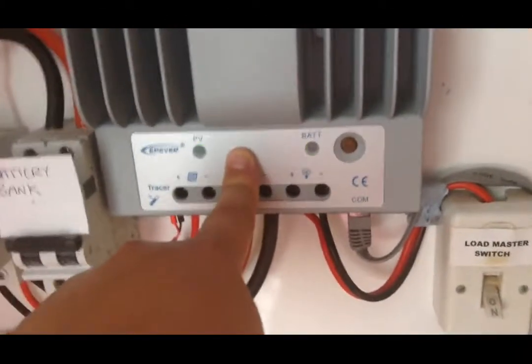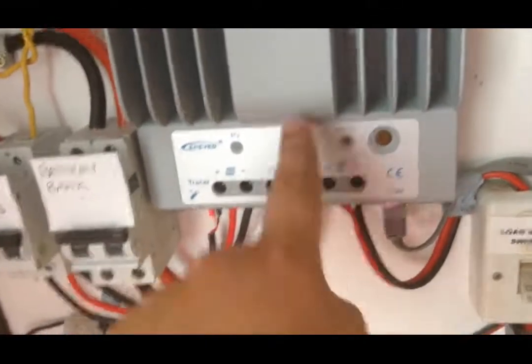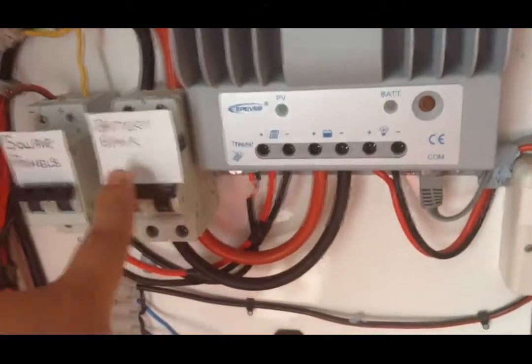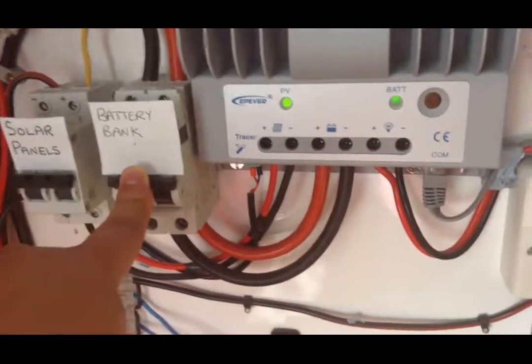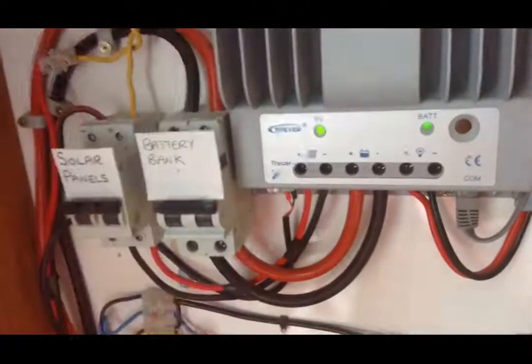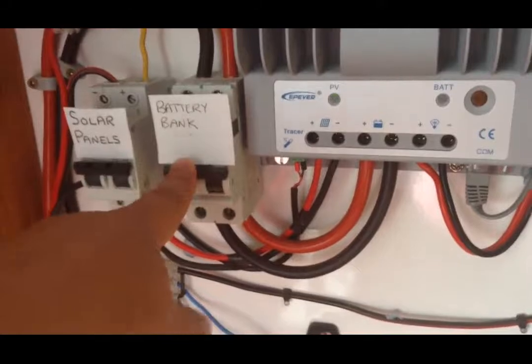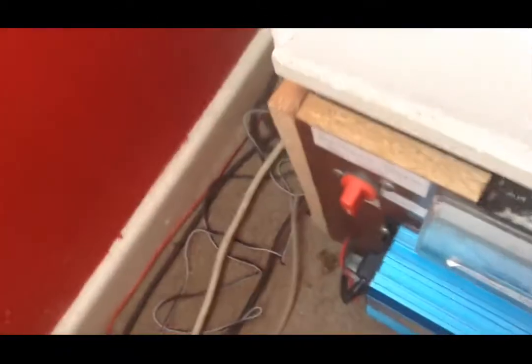The charge controller charges the batteries through this battery lead here, go through here to a switch and a breaker. So if a fault occurs in here, this trips out and disconnects this. Also acts as a switch, so I can turn it off if I want to work on other things. Then we have the main lead going down to the battery bank, which is down there, and there's a main switch here to disconnect the batteries if I want to work on the rest of the system, or if I have an issue and I quickly need to disconnect the batteries. So that's how that works.